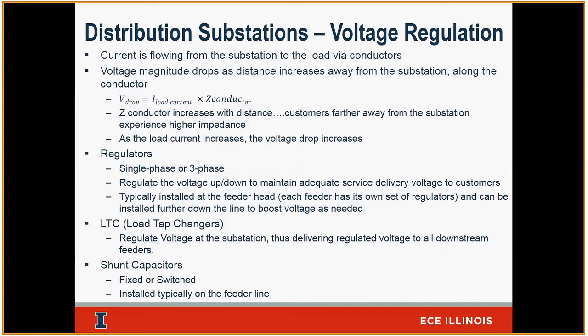That way I don't have to design every circuit. I don't have to call every engineer and figure out what their voltage regulators are set to. The device that regulates the voltage is a voltage regulator. It's a small transformer. You tell it what you want it to regulate the voltage to, and it will step up and down within its coils to boost or buck the voltage. So as the source fluctuates, it fluctuates as well to maintain that set point. So that's what utilities did. They said, okay, we're going to do 125 at the substation. That way we don't risk anybody at the end of the line seeing any low voltage.